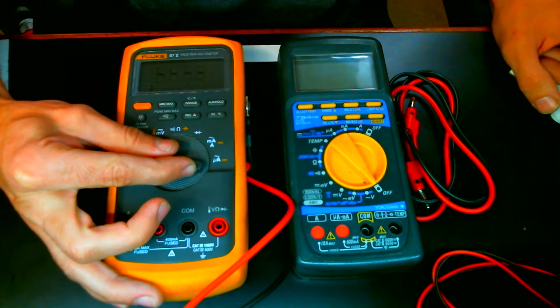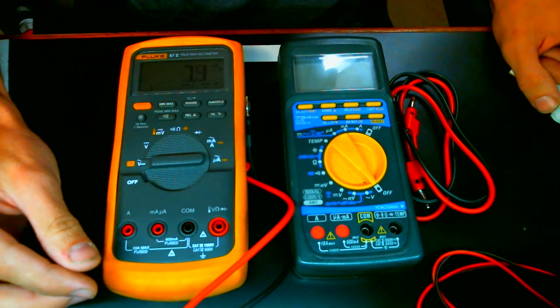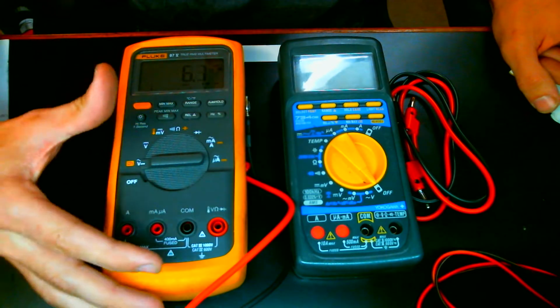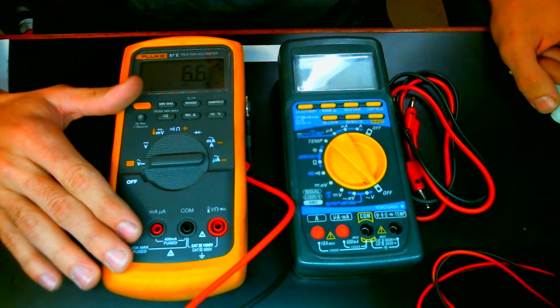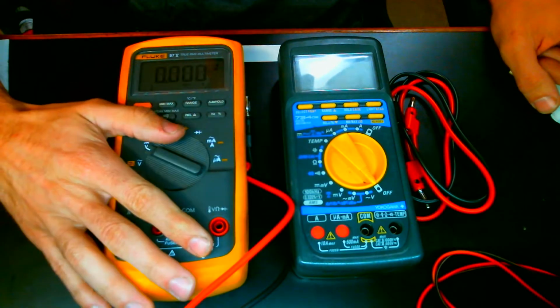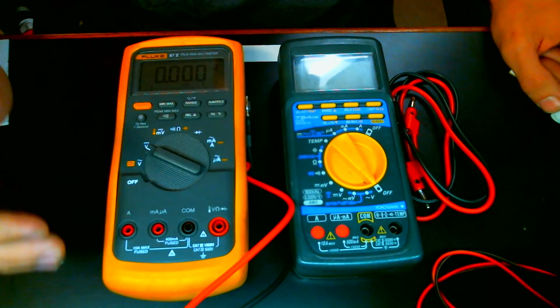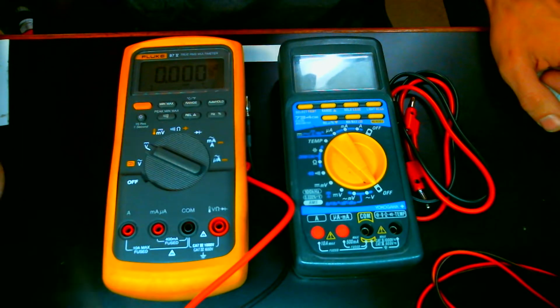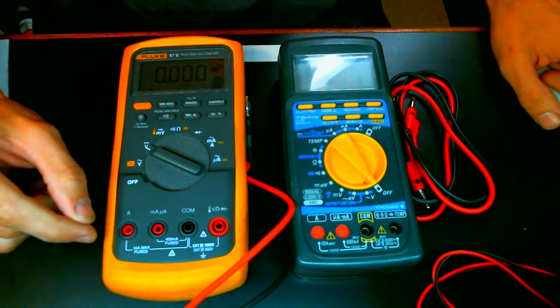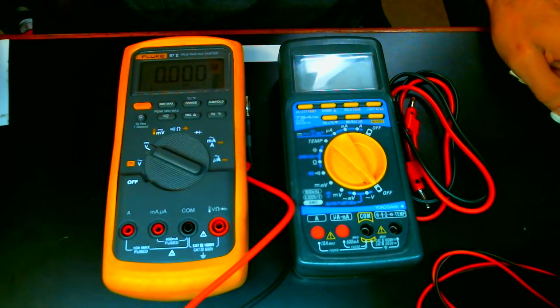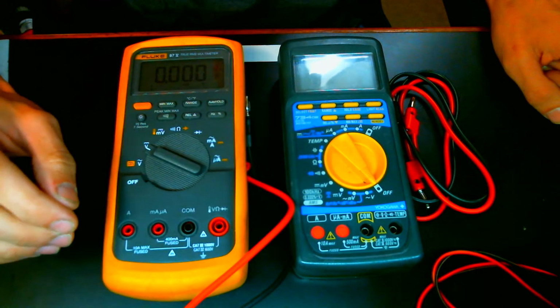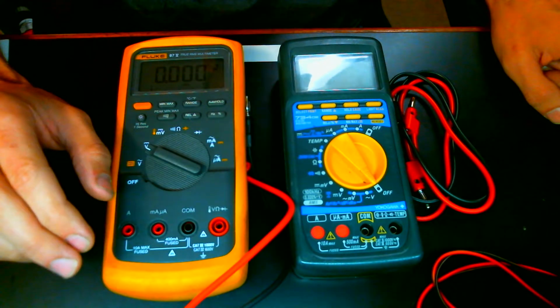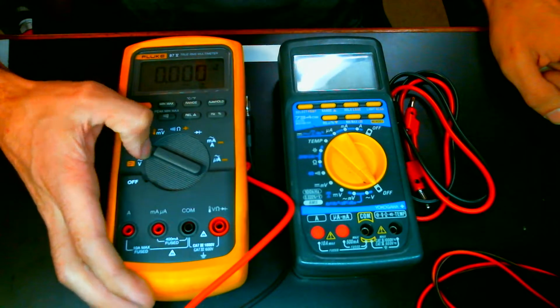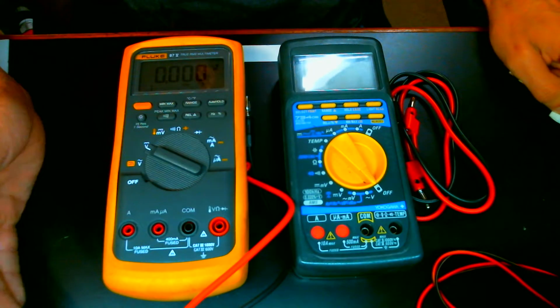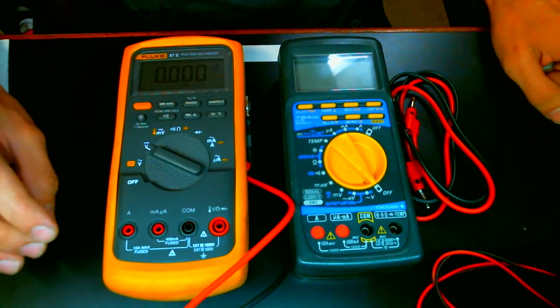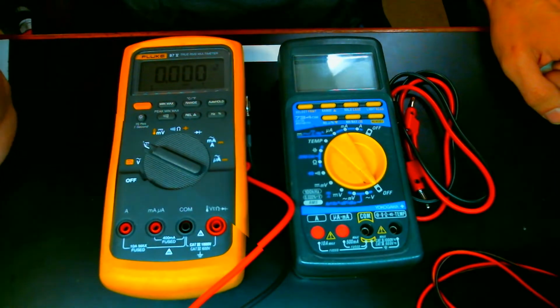The second form of calibration is where they're actually going to go in and adjust it. To me, this is whenever you really get into the calibration of things. It's because you check this meter, like the Keithley 192, and it's off. It's out of spec. You have to go in and adjust that and get it accurate. Maybe not you, maybe the service company. Some people do their own in-house calibrations. I don't really recommend it. I recommend getting third-party calibrations if required, because if you ever have any audits or anything like that, in-house calibrations are often suspect by the...